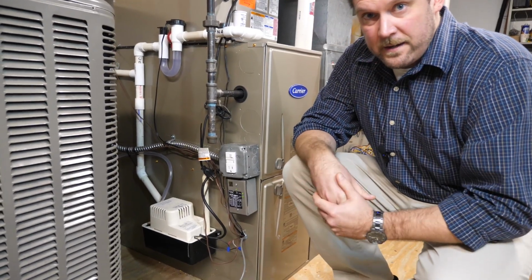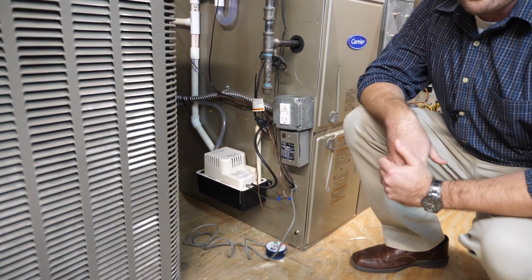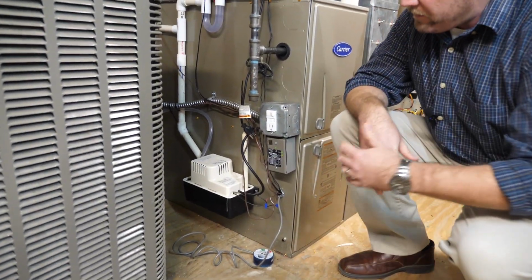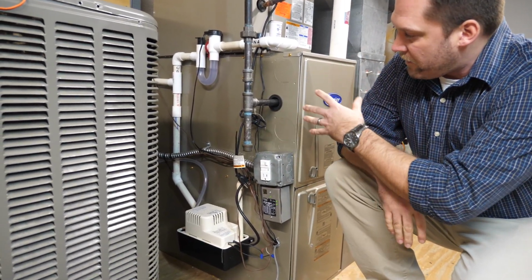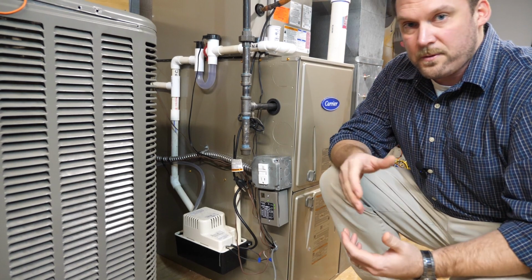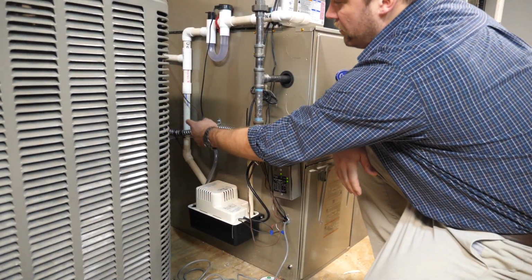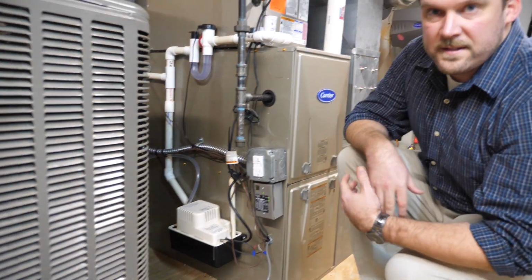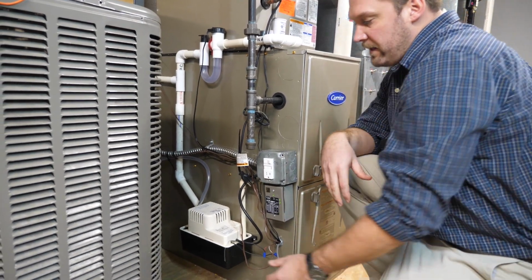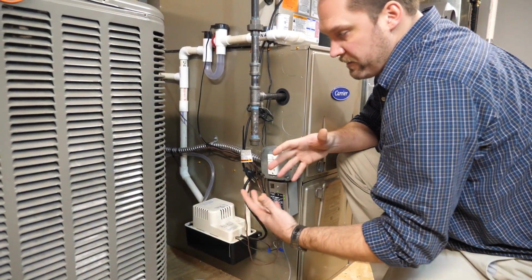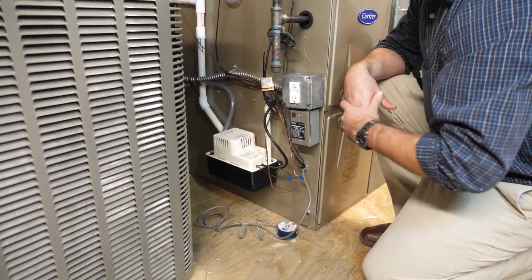All right, the second issue would be a condensate pump. It's this guy on the side of your furnace. Sometimes it's on the ground itself, but all the moisture or water that the humidifier, furnace, all those things produce go into this trap, and then it gets pumped through this tube to a drain or a sink or something close to the area. Usually if these fail or something stops working on it, water comes outside of here and just kind of gets onto the floor.